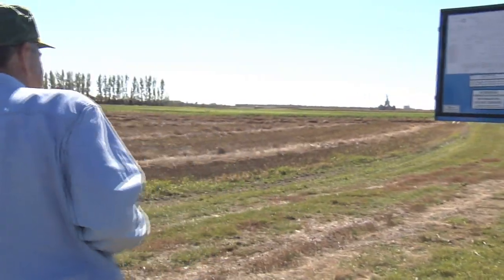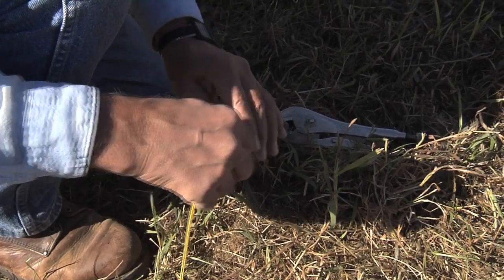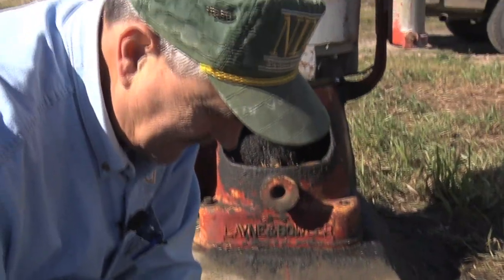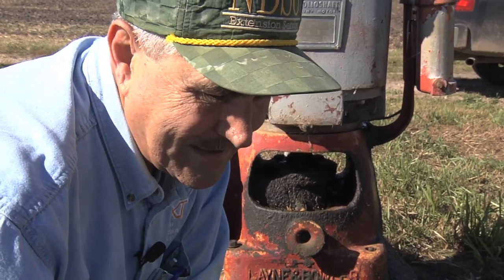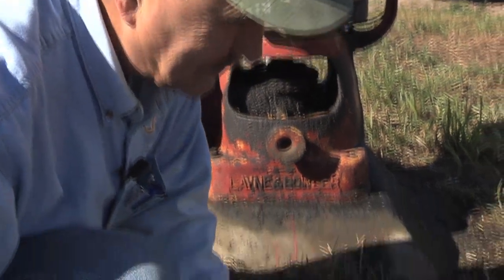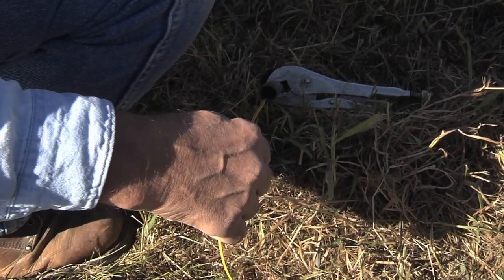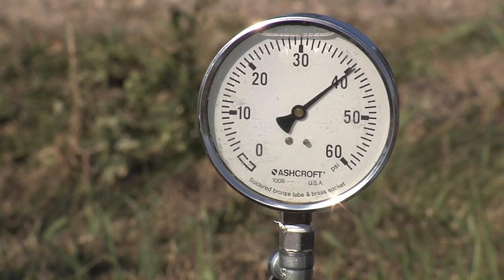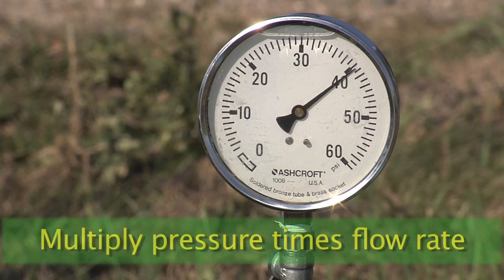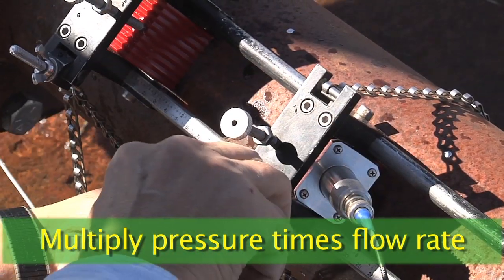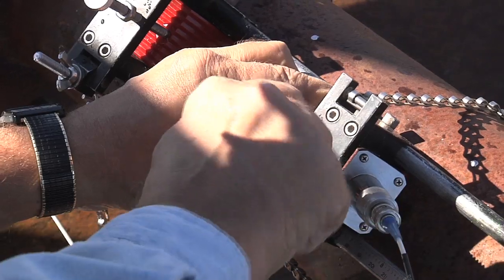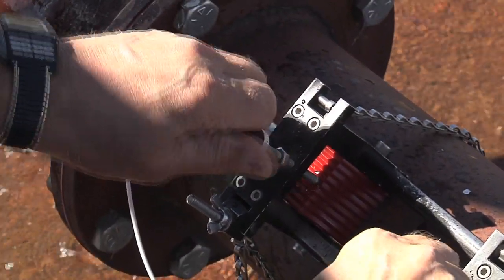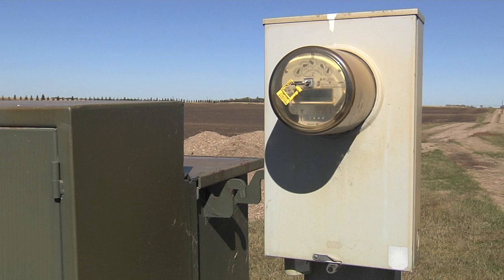Is that correct? Nope. If the end gun were on, it would probably be drawing more, but we don't want to test that anyway. Now that the pump is running, we measure the flow rate. I need to know what the pumping water level is, because the pump is lifting it from that depth up to this point, and then my pressure gauge is telling me what the pressure is. Between that I can get the total head, and then if I multiply that times the flow rate, I can estimate how much actual power is in the water.